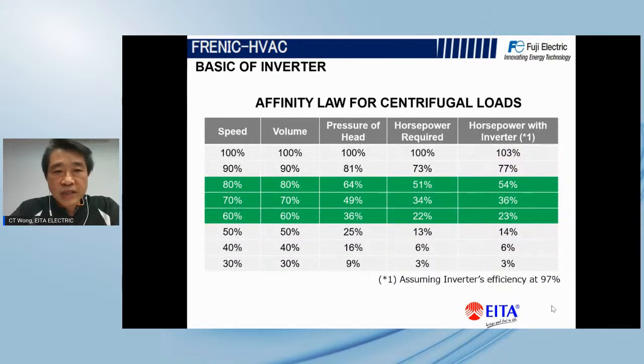And over here, I do a quick summary. As I say, if you cannot vary the speed of your pumps, there is no point in considering inverters, because the inverter efficiency is probably 97%, or maybe the best you can go is 98%. You would still consume more energy because of the inverter efficiency. But when you are able to reduce the speed, like 10%, or you can see the highlight over here in green, from 80% speed the energy consumption probably only needs 54% of the energy. So this is the beauty of inverters: they can help you save energy.